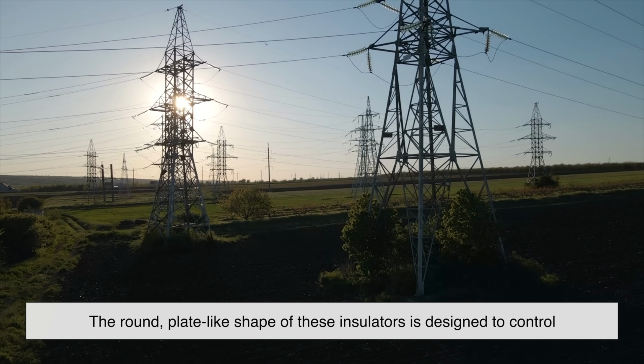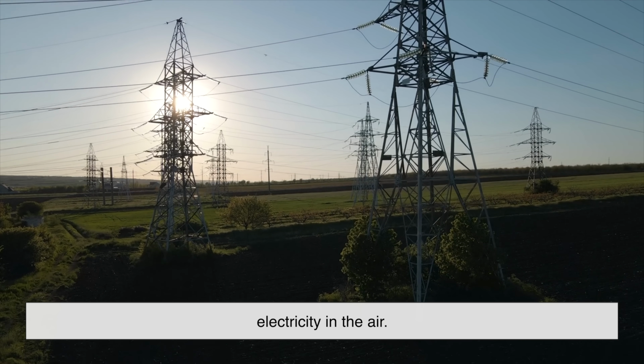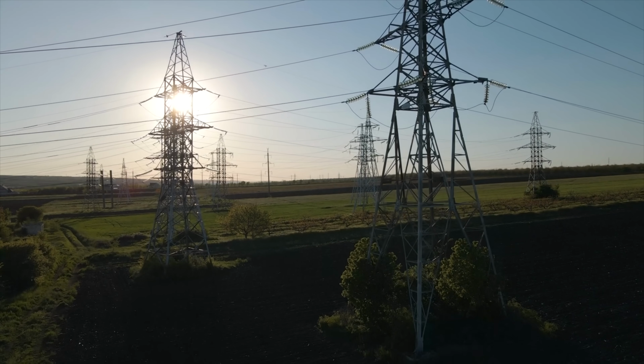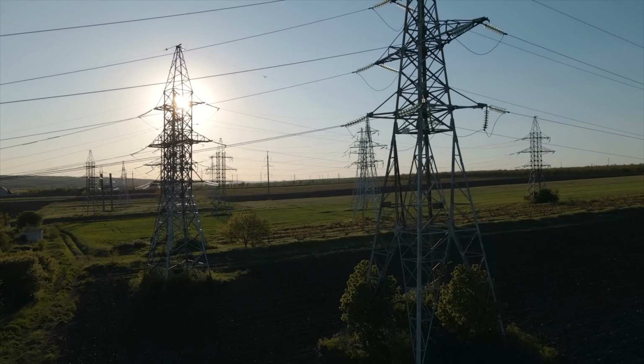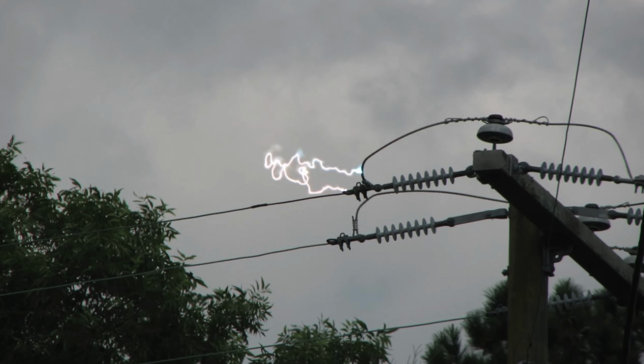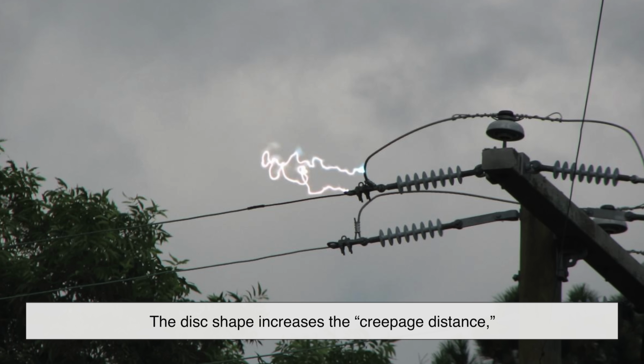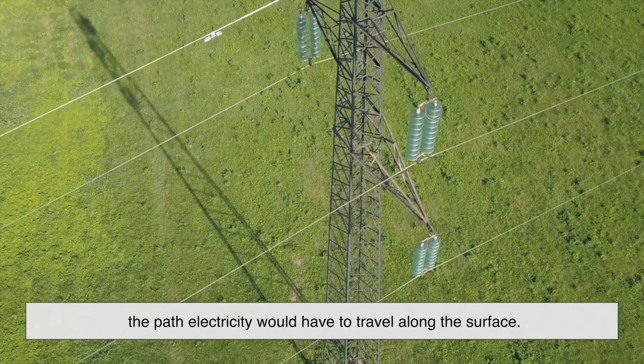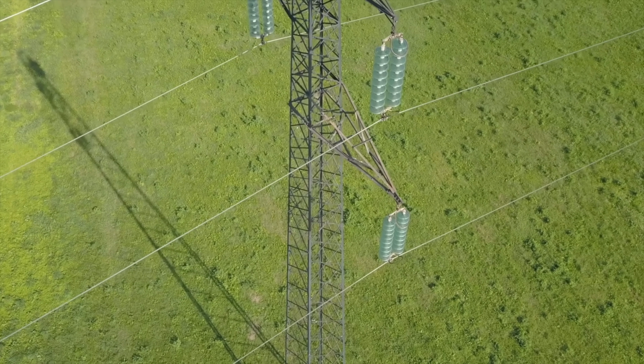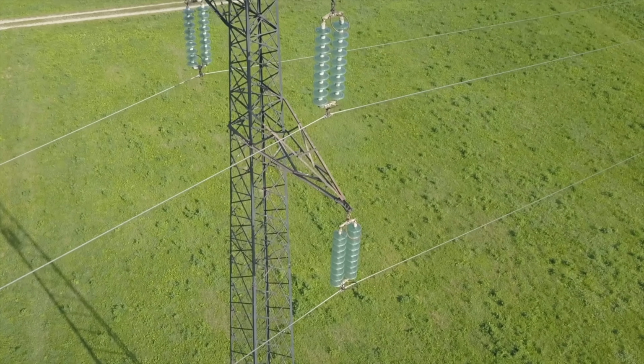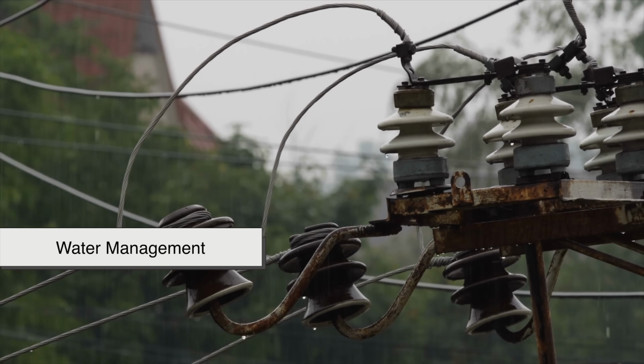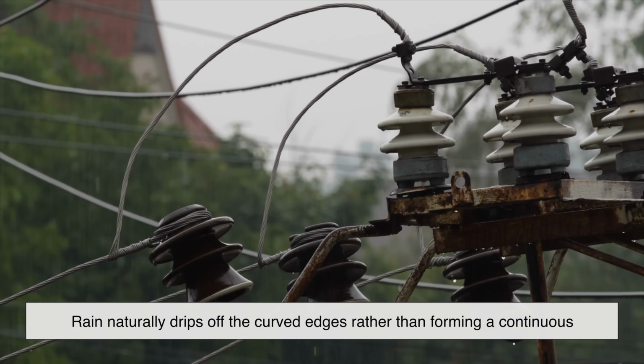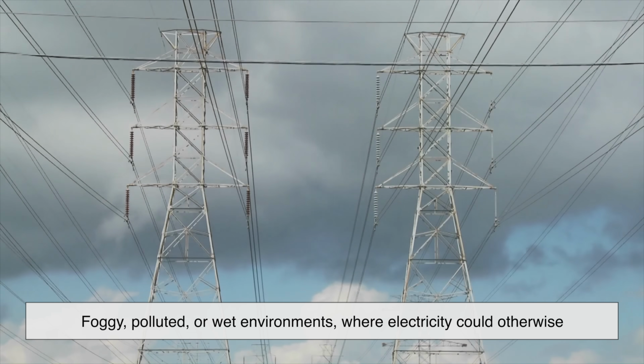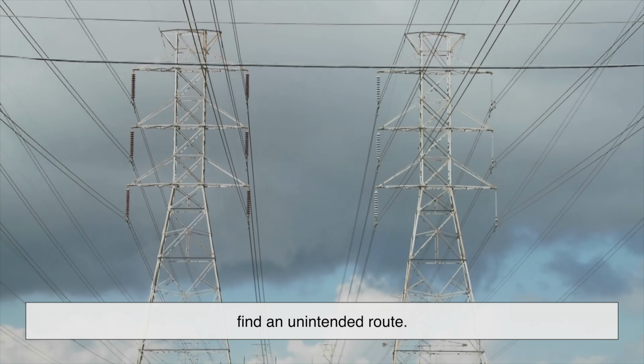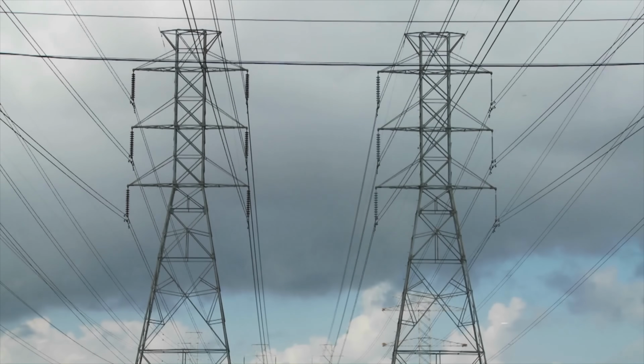The round, plate-like shape of these insulators is designed to control electricity in the air. High-voltage electricity doesn't only travel through wires, it can leak along insulator surfaces if conditions are right, a phenomenon called electrical flashover. The disc shape increases the creepage distance, the path electricity would have to travel along the surface. Longer paths make it harder for current to escape. The shape also helps water management. Rain naturally drips off the curved edges rather than forming a continuous conductive path. This is essential in foggy, polluted, or wet environments, where electricity could otherwise find an unintended route.